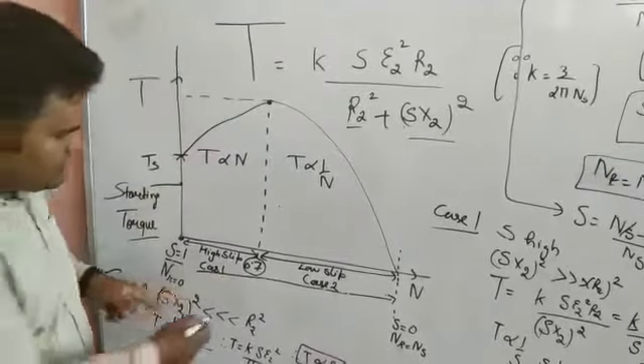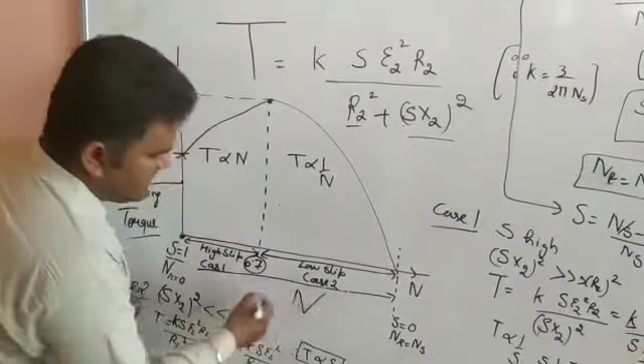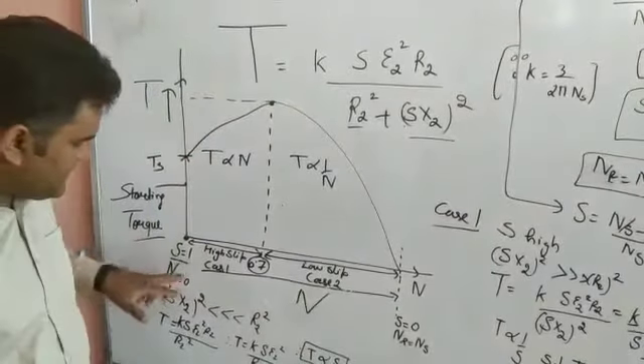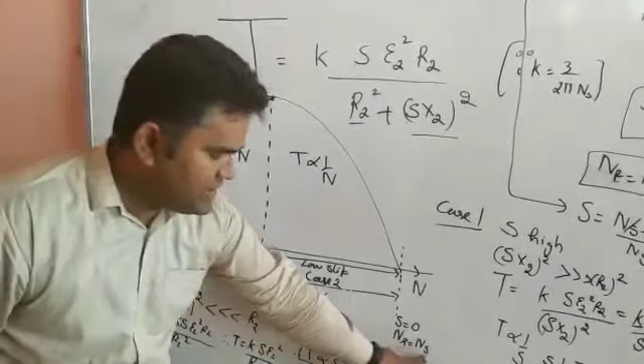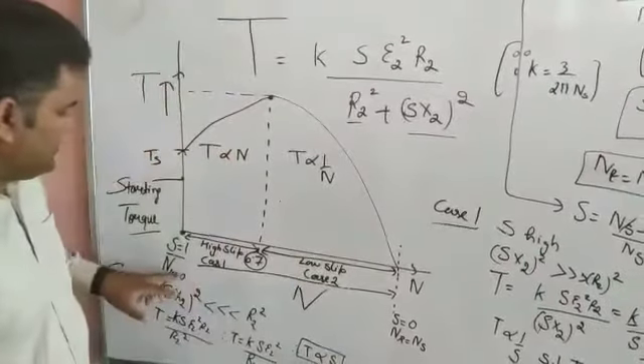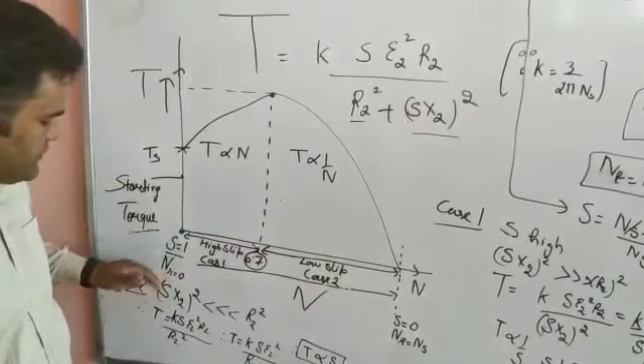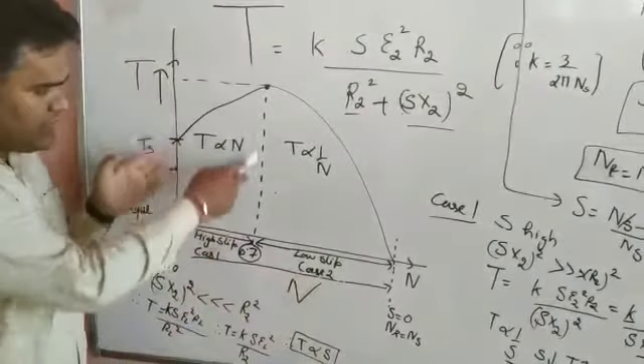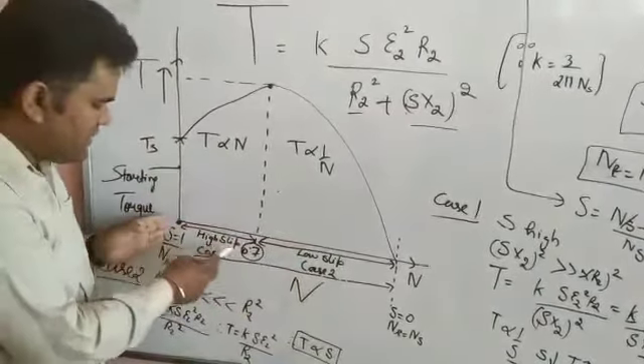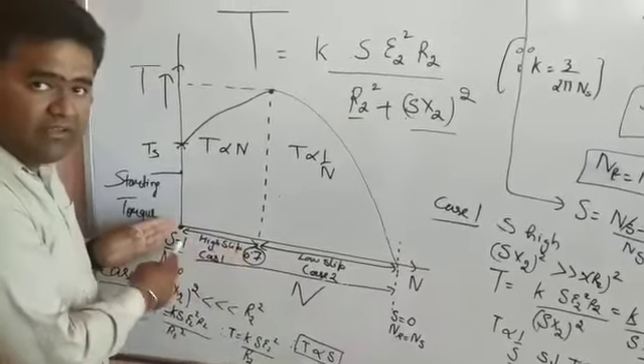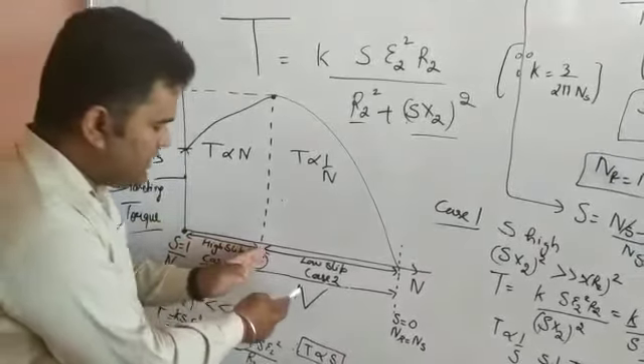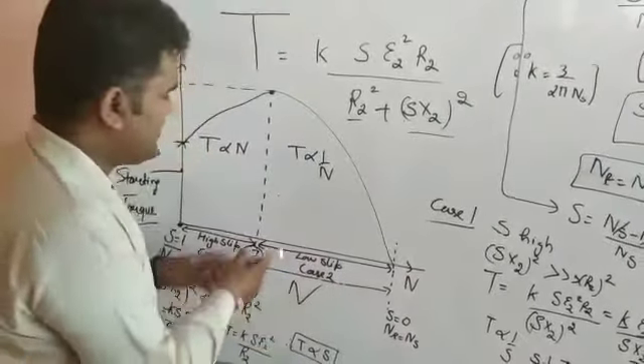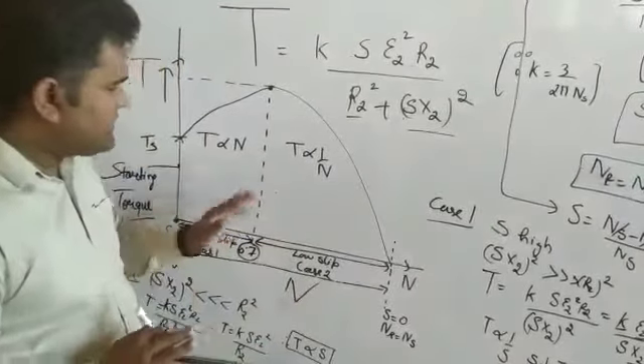So the torque-speed curve has speed on the x-axis and torque on the y-axis. Speed starts from 0 here and goes up to synchronous speed. When slip is 1, speed is 0, and when slip is 0, speed equals synchronous speed. I divide this curve into two portions: the high slip region and the low slip region from about 0.7 down to 0.